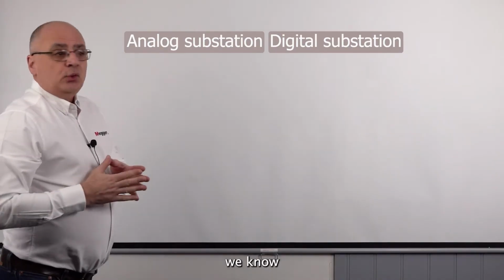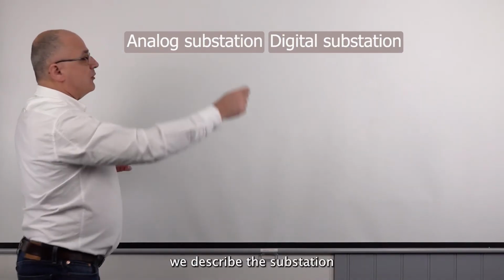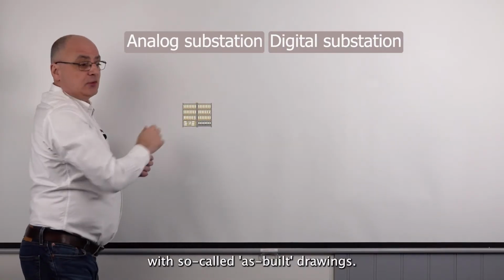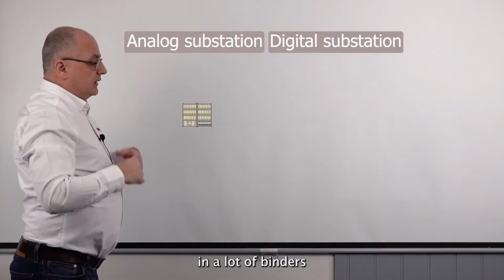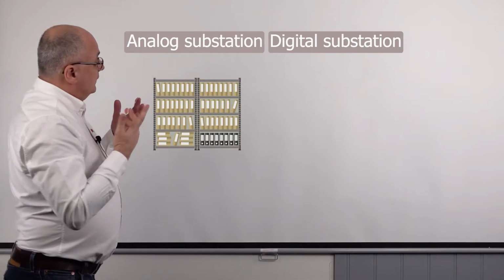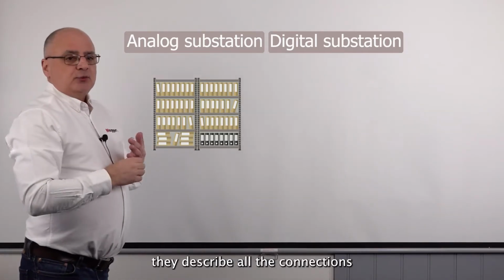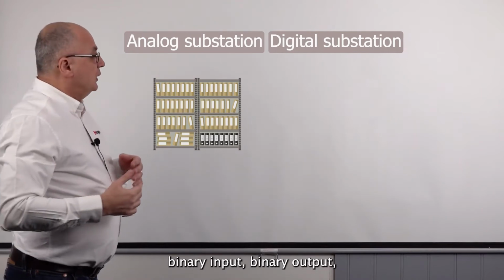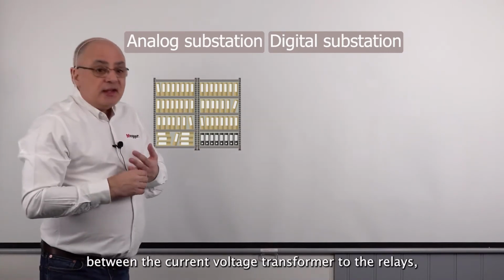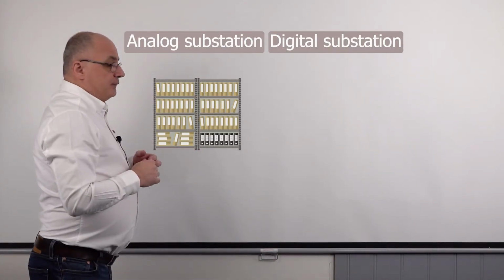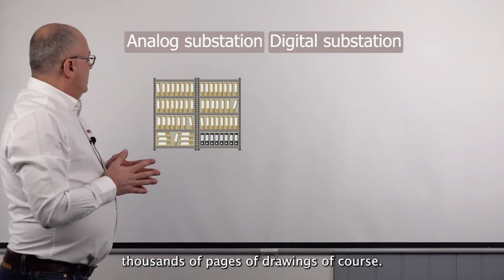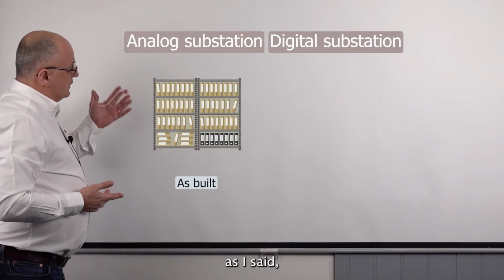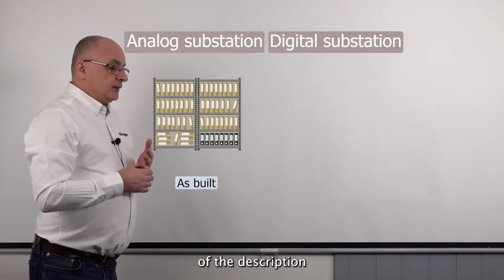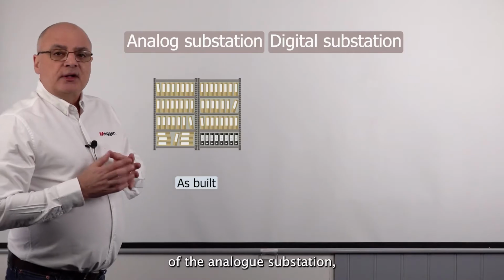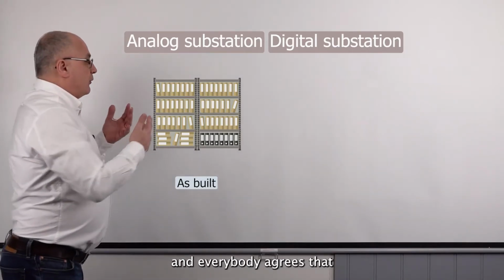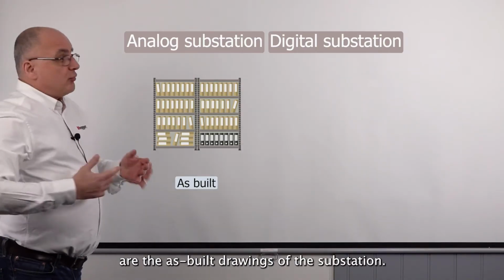Considering the analog substation, we know well how to describe it: with so-called as-built drawings. These are many drawings in many binders, describing all connections between relays, binary inputs, binary outputs, analog connections from current and voltage transformers to relays, and connections to circuit breakers—thousands of pages of drawings. The as-built drawing is a very important part of the description of the analog substation, and everybody agrees it's part of the delivery.